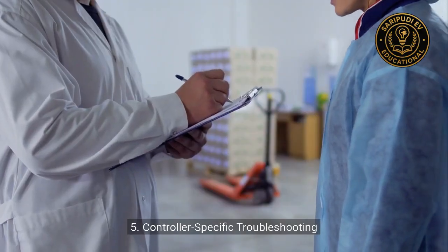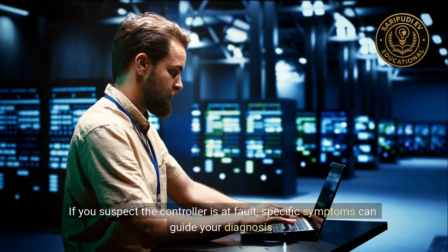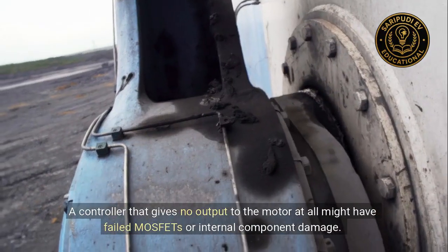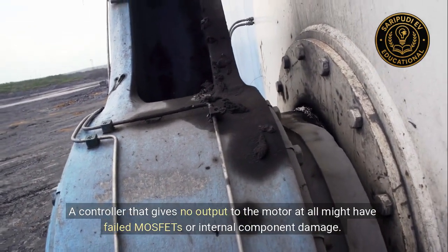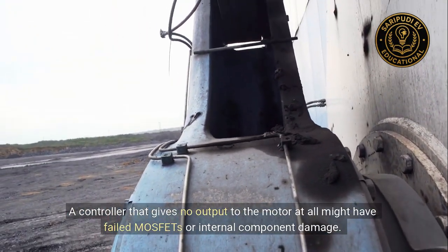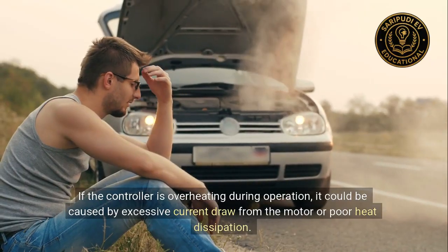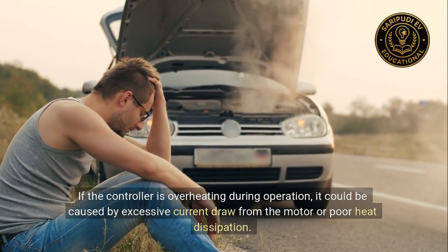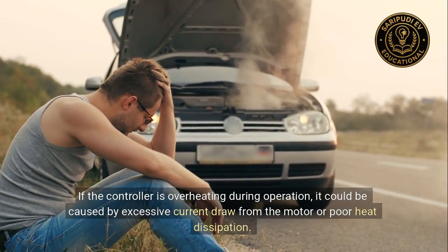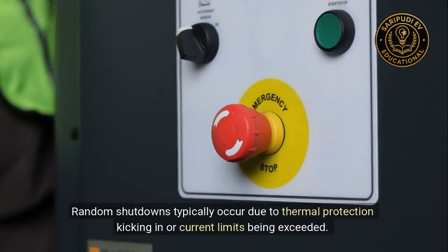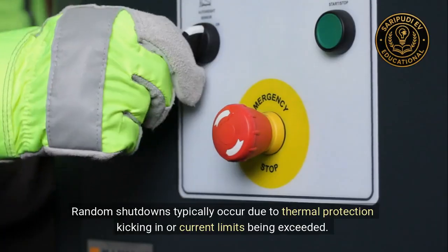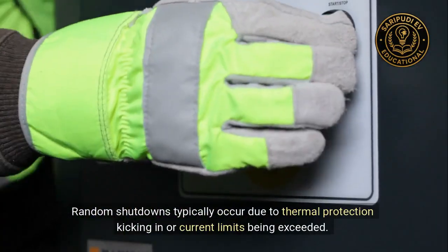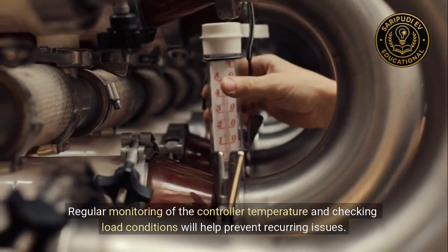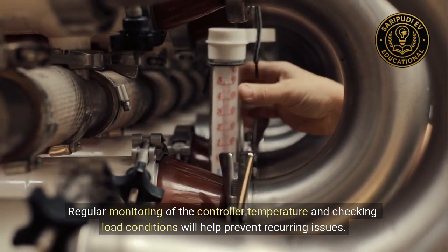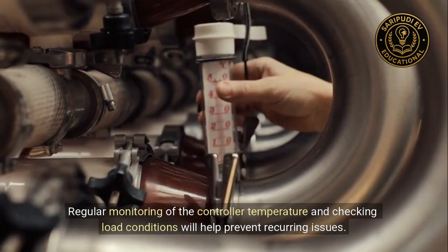5. Controller-specific troubleshooting. If you suspect the controller is at fault, specific symptoms can guide your diagnosis. A controller that gives no output to the motor at all might have failed MOSFETs or internal component damage. If the controller is overheating during operation, it could be caused by excessive current draw from the motor or poor heat dissipation. Random shutdowns typically occur due to thermal protection kicking in or current limits being exceeded. Regular monitoring of the controller temperature and checking load conditions will help prevent recurring issues.